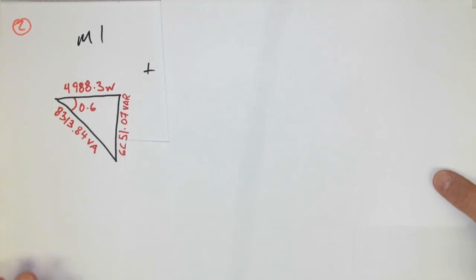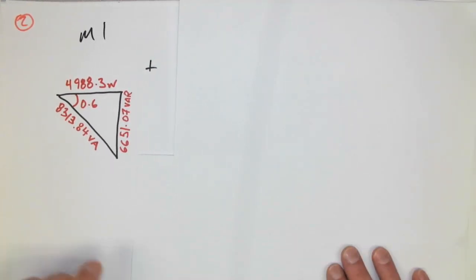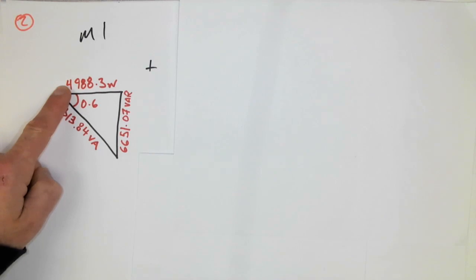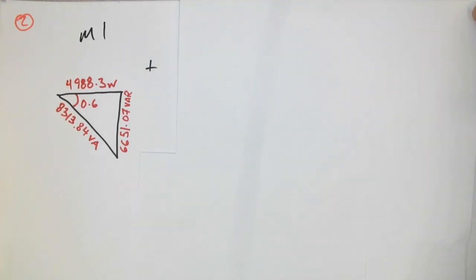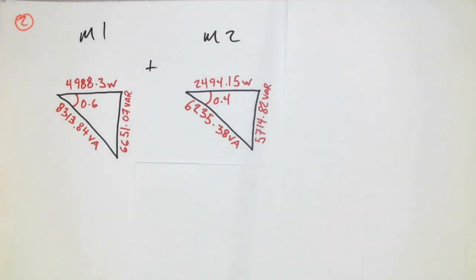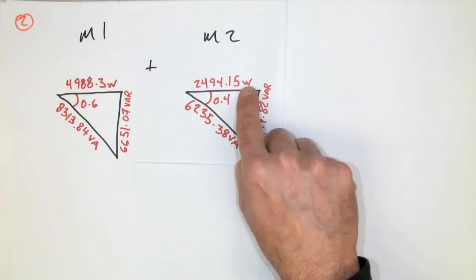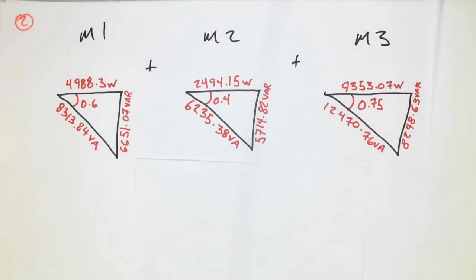Here is our first power triangle for motor one — we have 8313.84 VA. I calculated that first, then used the power factor to get my watts and Pythagoras to get my VARs. For the second motor, same thing: I calculated the VA first, used the power factor to get the watts, and calculated with Pythagoras my VARs. And finally, the last one — it's a pattern; we're doing the same thing every single time.